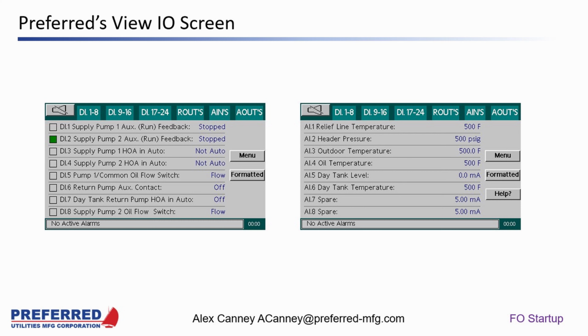If you don't have the cloud monitoring software, our alarm history isn't the same as the View IO screen. It's not every single status, but our history for alarms is great. We have statuses in black text, and for any alarms, when they come in, it's in red text. We also have a time and date stamp in green when it clears. So it gives you a lot of historical information. If somebody on the midnight shift decides to cancel an alarm 11 times, you're going to see all of that. So it doesn't necessarily record and trend all of the View IO, but we do give you a lot of historical information.